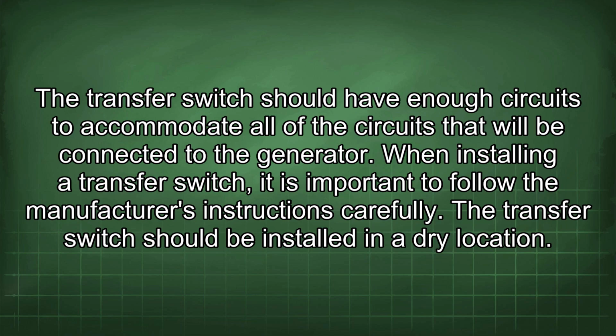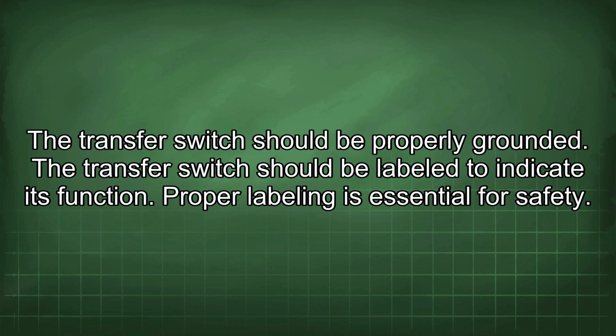When installing a transfer switch, it is important to follow the manufacturer's instructions carefully. The transfer switch should be installed in a dry location. The transfer switch should be properly grounded. The transfer switch should be labeled to indicate its function. Proper labeling is essential for safety.